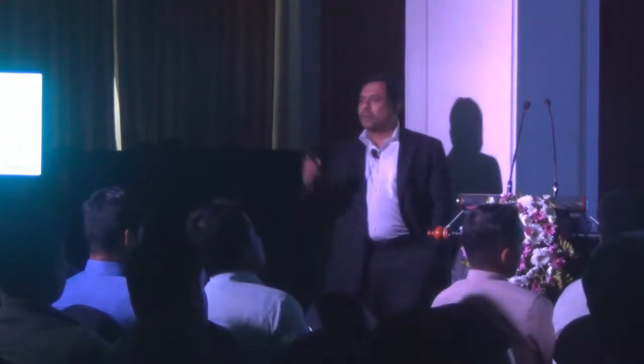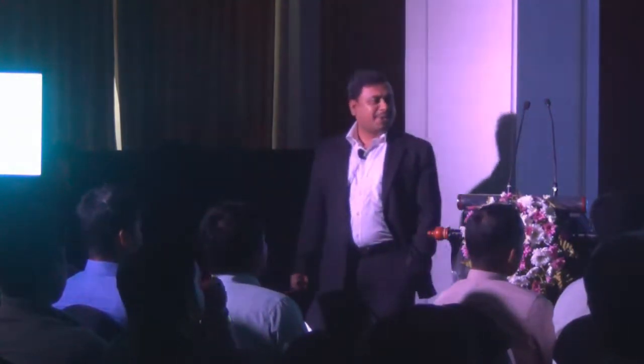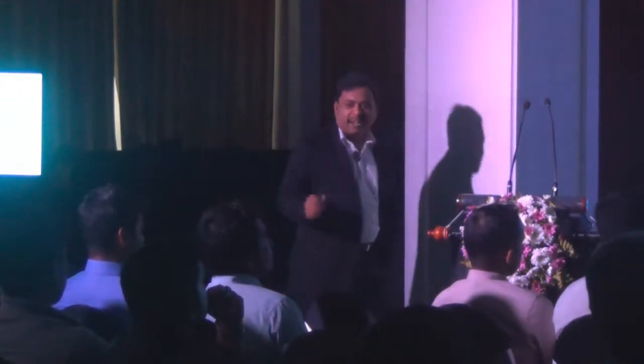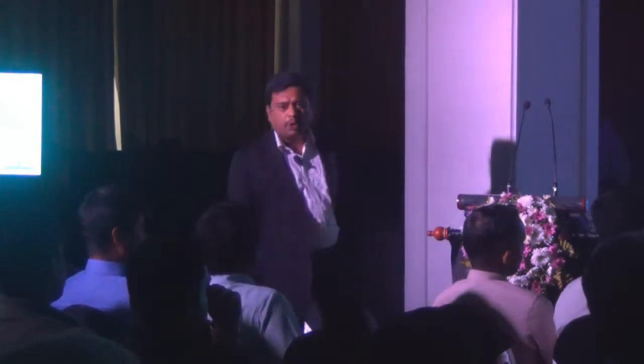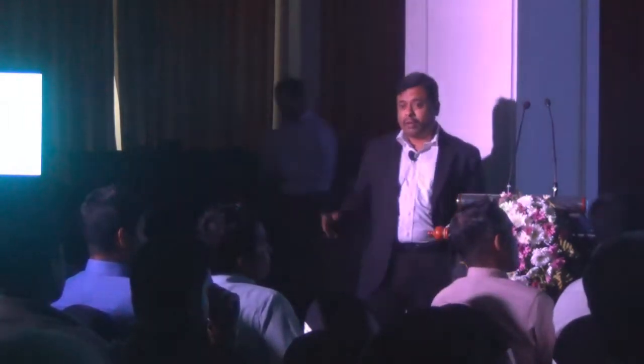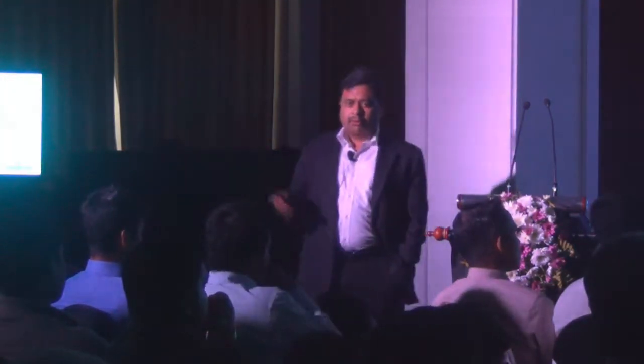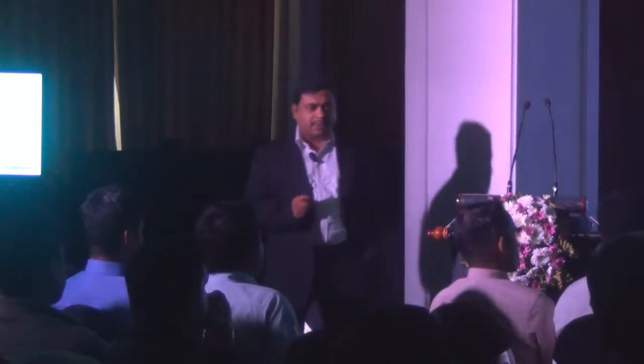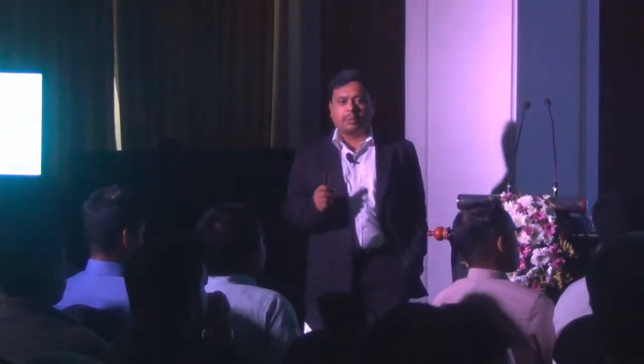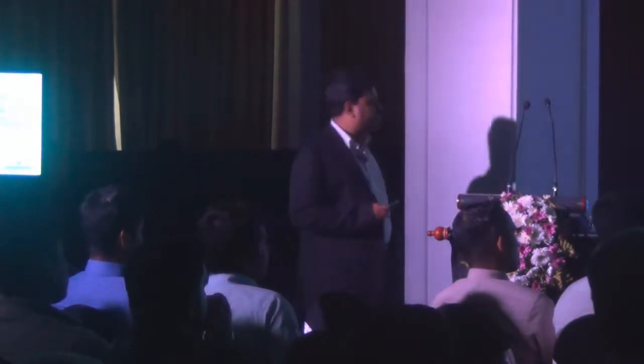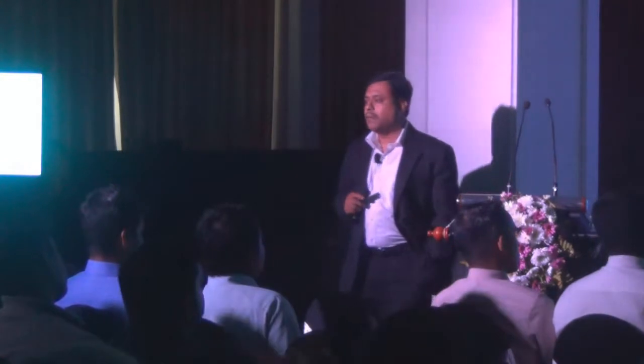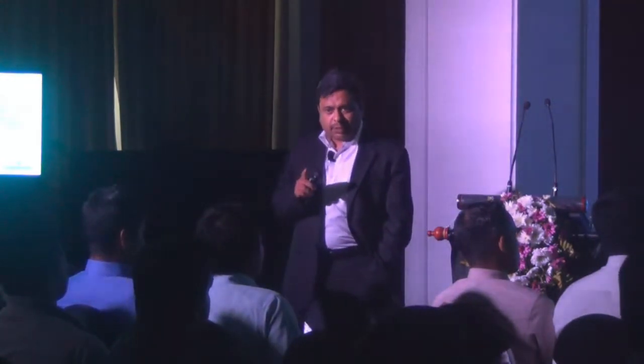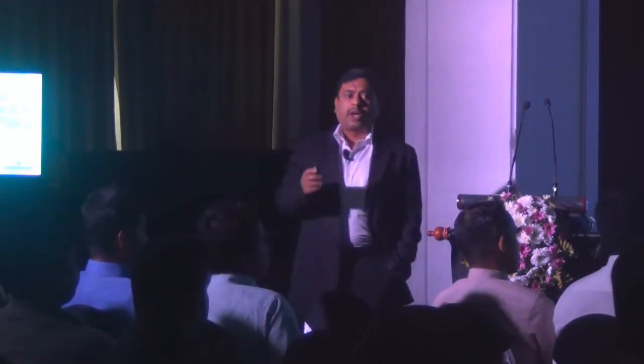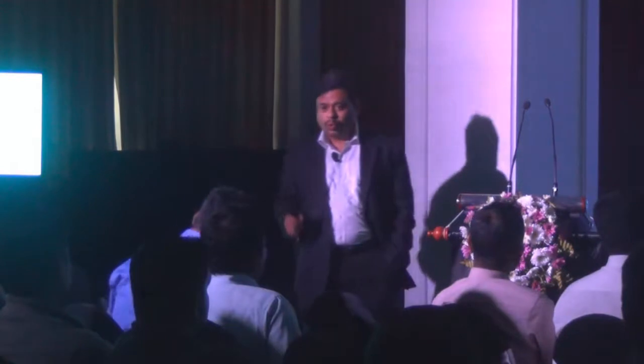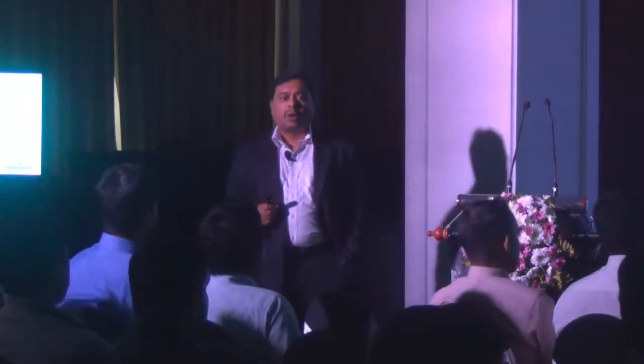So now, after 10 to 15 slides on power, we also have some interesting products where we are again pioneers. These are called PPCs, the electrical PDUs. These PDUs are available from 15 kVA to 800 kVA and are used inside your data centers. So we will not have any panels; we can use the PPCs. The advantage is you can monitor each breaker socket level completely with these PPCs. One more advantage is that we can provide them with or without an isolation transformer. And you can keep the PPC very close to your load, so that efficiency will be very high and your loss will be reduced heavily.